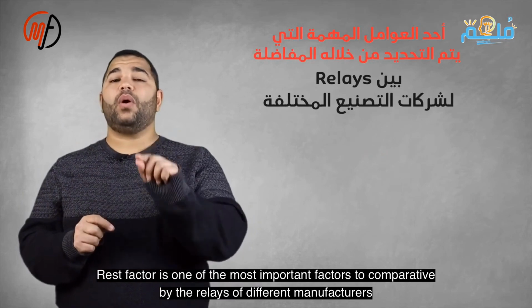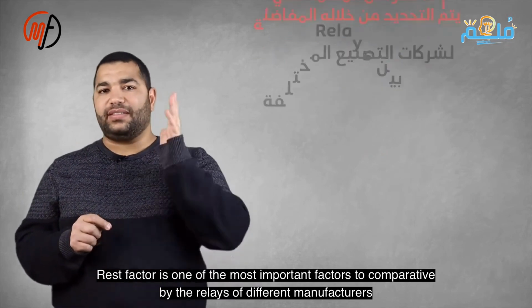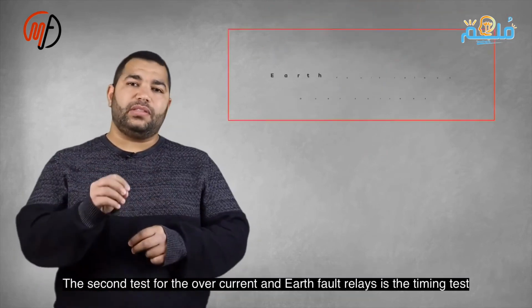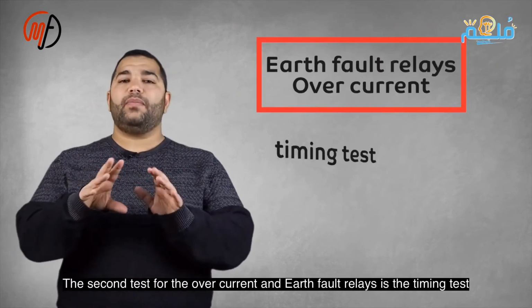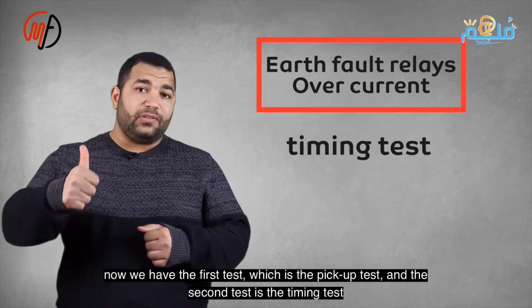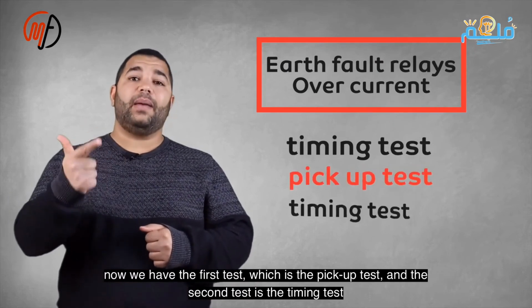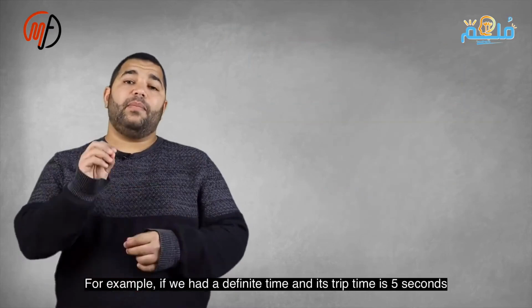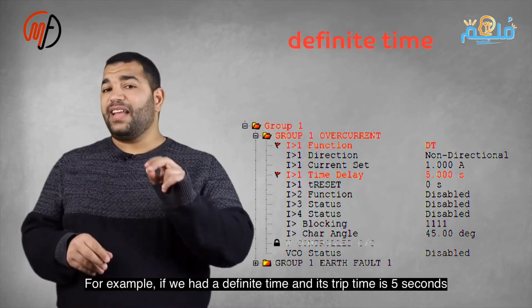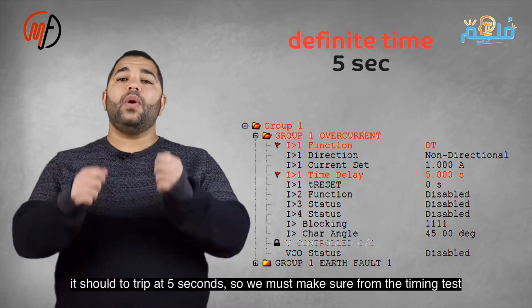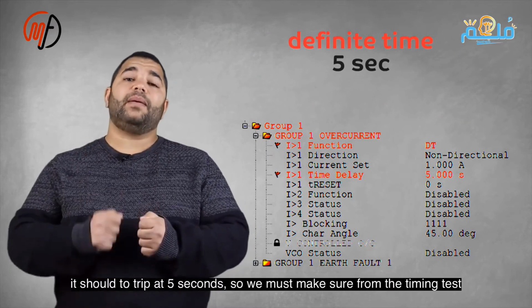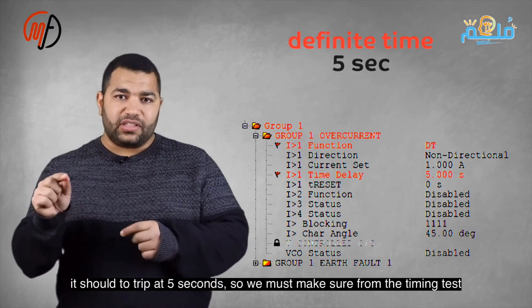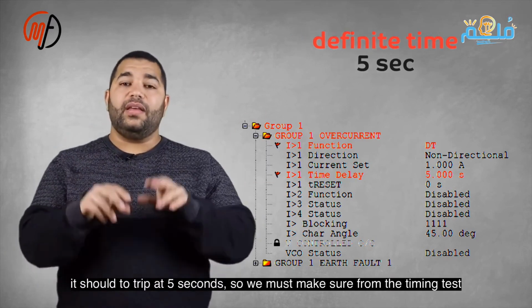The second test for overcurrent and earth fault relays is the timing test, following the pickup test. For instance, with a definite time relay set to trip in 5 seconds, it must trip precisely at 5 seconds, verified by the timing test. If the relay uses an inverse time curve, specific equations calculate the expected trip time. For a normal inverse curve, knowing the TMS value is essential. The trip time varies with current. Higher fault currents result in shorter trip times.